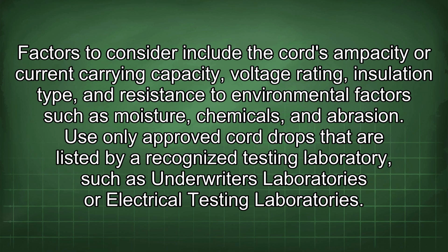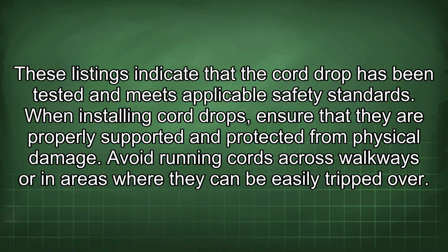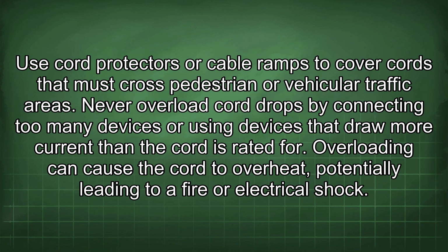Use only approved cord drops that are listed by a recognized testing laboratory, such as Underwriters Laboratories or Electrical Testing Laboratories. These listings indicate that the cord drop has been tested and meets applicable safety standards. When installing cord drops, ensure that they are properly supported and protected from physical damage. Avoid running cords across walkways or in areas where they can be easily tripped over. Use cord protectors or cable ramps to cover cords that must cross pedestrian or vehicular traffic areas.